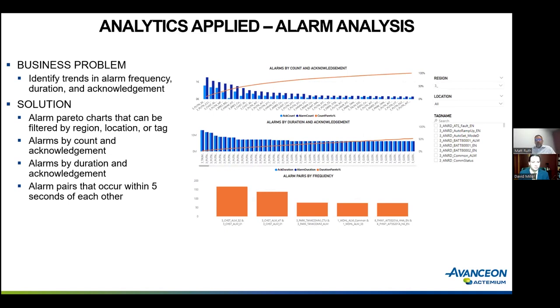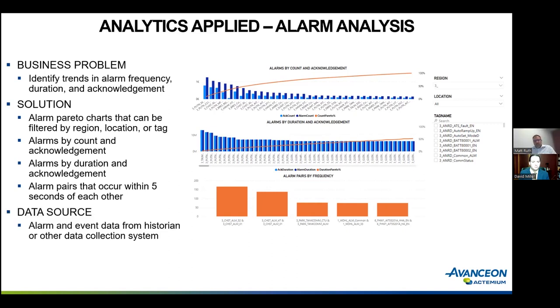This is a good example from a water/wastewater facility showing different chemical alarms — which ones are most active, most frequent at each location, and which ones occur within five seconds of each other to see if they're related. It gives you insight you wouldn't have by just looking at the alarm list or historical alarm list with its long text-based string of information. This readily available data from the historian or alarm and event database, difficult to manually dissect, is a great application for analytics.